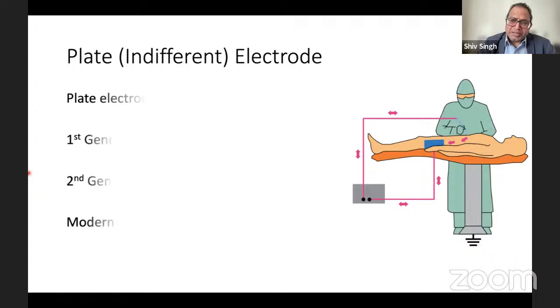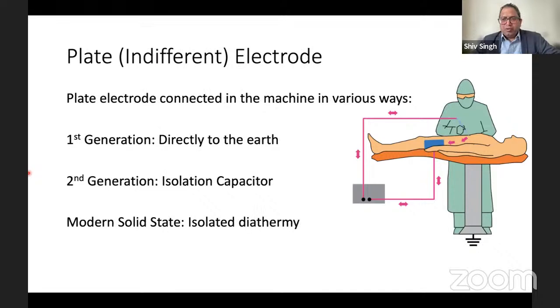Now this is where all the confusion actually occurs. People talk about earth being dangerous, or what is the isolation capacitor, and the new diathermies. These are basically various generations of the diathermy. In the first generation, the plate was connected directly to the earth. In the second generation, they used isolation capacitors, and I'll tell you how it was used. But modern day diathermy uses isolated power systems, the one which we have talked about, which is earth-free.